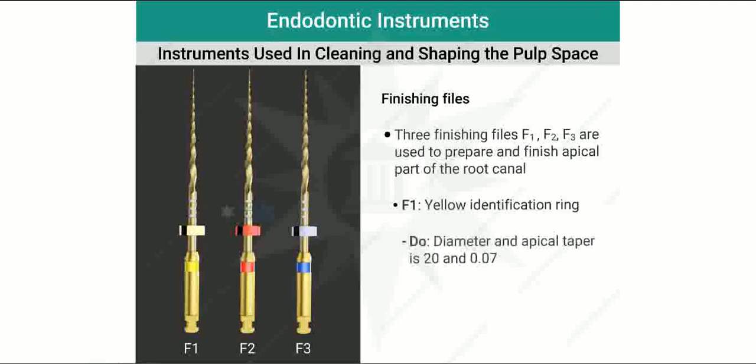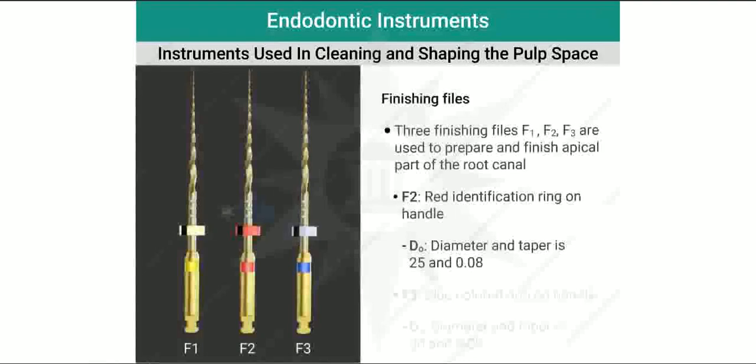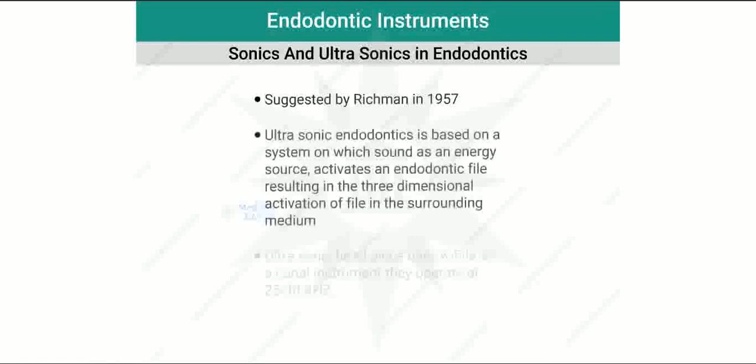And then sonics and ultrasonics in endodontics. It was first suggested by Richman in the year 1957. Ultrasonic endodontics is based on a system in which sound as an energy source activates the endodontic file, resulting in 3-dimensional activation of the file in the surrounding medium. This ultrasonic handpiece uses K files as a canal instrument. They operate at a speed of 25 to 30 kHz.